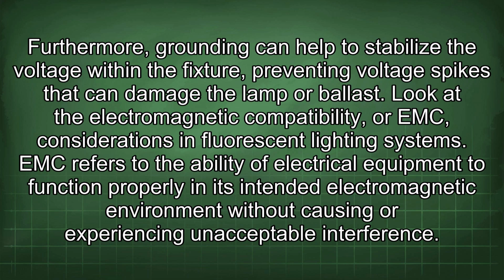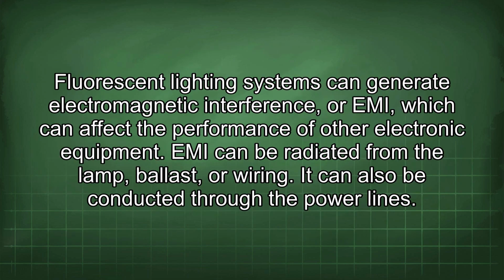Look at the electromagnetic compatibility, or EMC, considerations in fluorescent lighting systems. EMC refers to the ability of electrical equipment to function properly in its intended electromagnetic environment without causing or experiencing unacceptable interference. Fluorescent lighting systems can generate electromagnetic interference, or EMI, which can affect the performance of other electronic equipment. EMI can be radiated from the lamp, ballast, or wiring. It can also be conducted through the power lines.